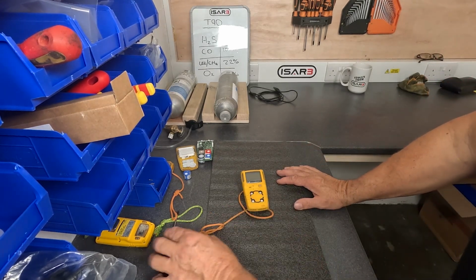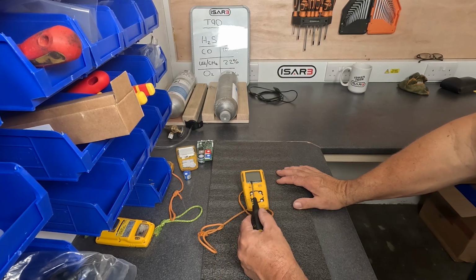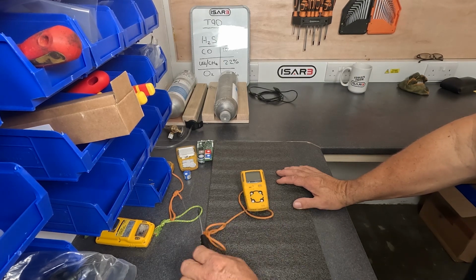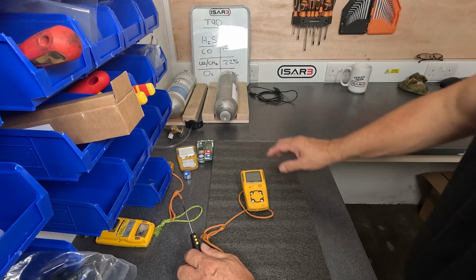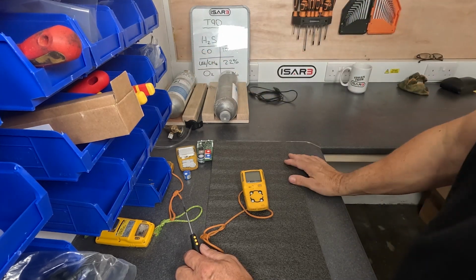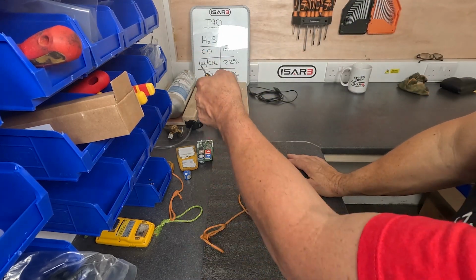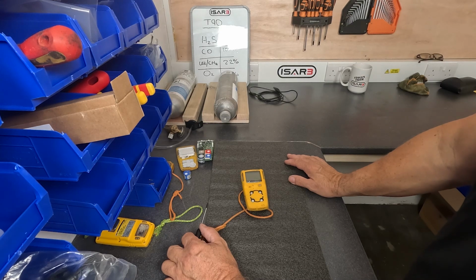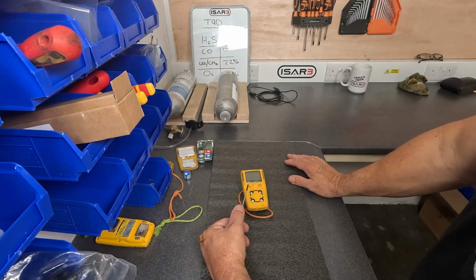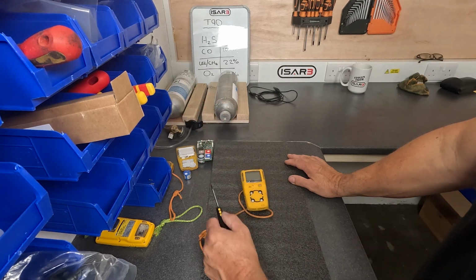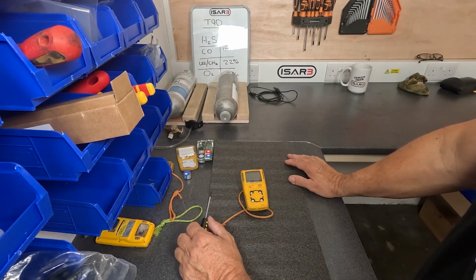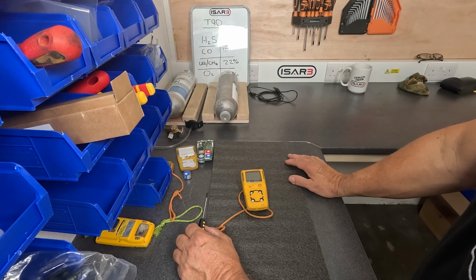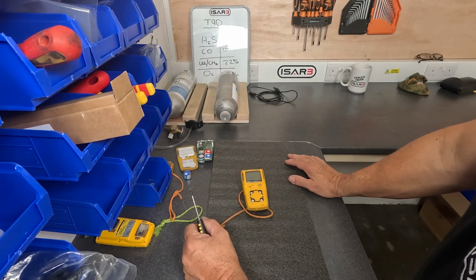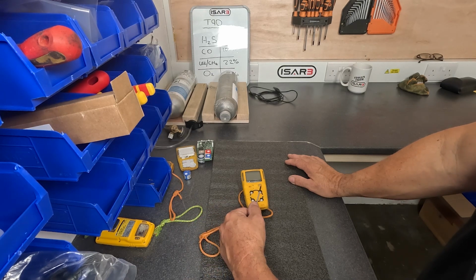So what do we do with this information? All right, the numbers that you got on here in terms of how accurate the gas detector is against the reference gas should be within 10% of the reference gas values. Otherwise, that sensor is out of spec. You can then bring them back, hopefully, by doing a calibration on site, and you can do that with exactly the same gas and exactly the same equipment. You just need to know how to calibrate it. That's all end user functionality.